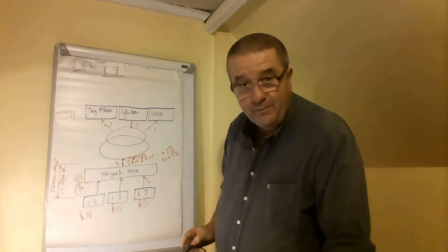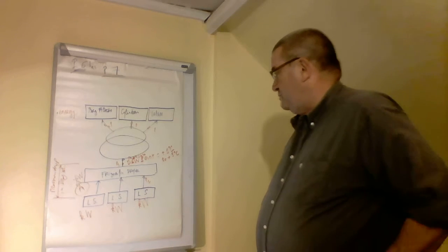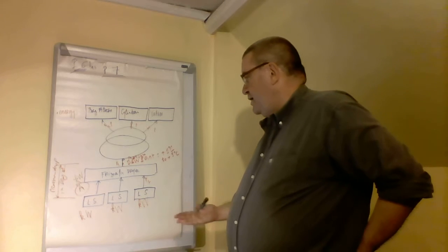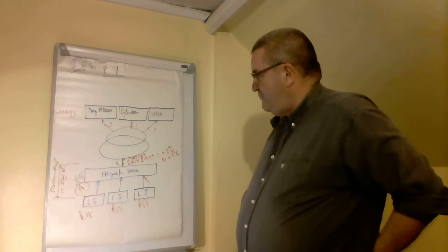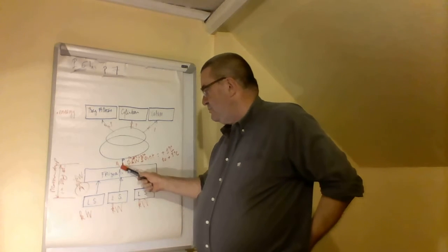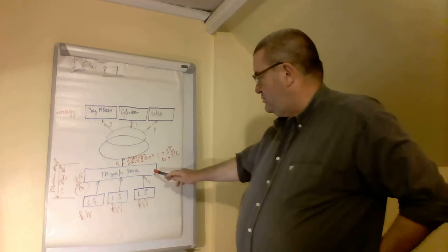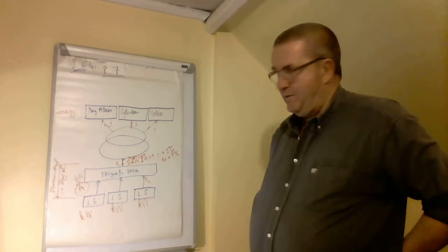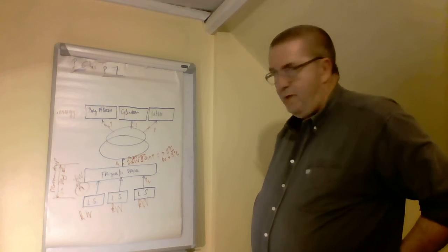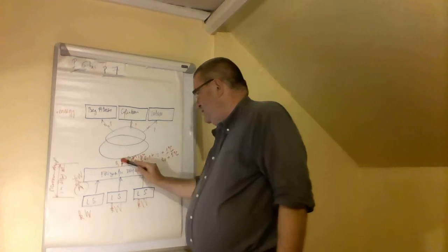Pressure drop in a dryer is usually around 150 to 200 millibar, according to how you size your dryer. If you have some filters to protect the dryer and some as a safety filter in case the condensate drain is not effective, then you may lose 1 bar. So you have here a very interesting measurement.